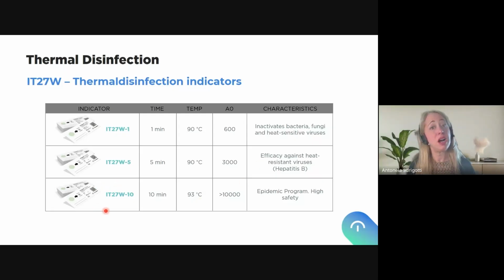And IT27W10, which is for the epidemic program. The A0 value here is more than 10,000, around 12,000, and is reached in 10 minutes at 93 degrees. This type of program is used when we have an outbreak and we don't know the microorganism that is generating this outbreak. So just in case, we add an extra disinfection guarantee to make sure that regardless of the origin of this microorganism, we will inactivate it. Okay? This is why we offer these three options for the three most used combinations of time and temperature to reach these specific A0 values.